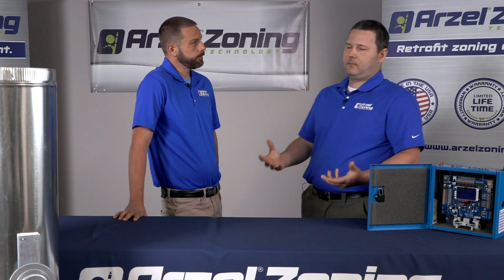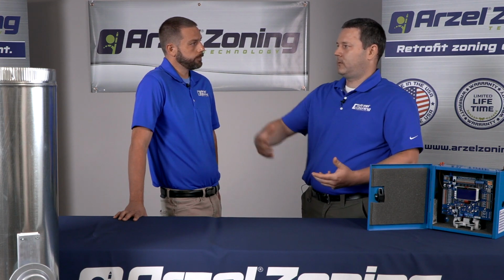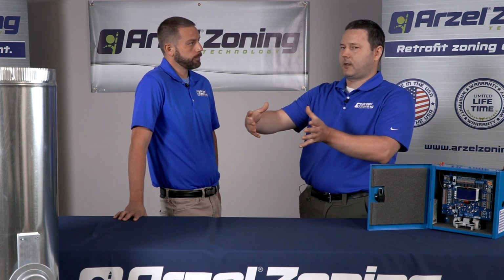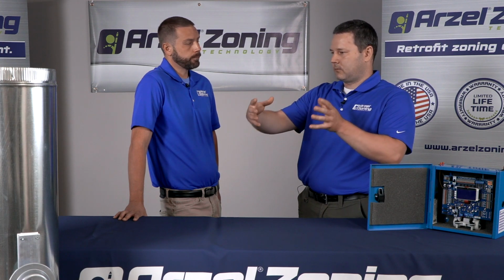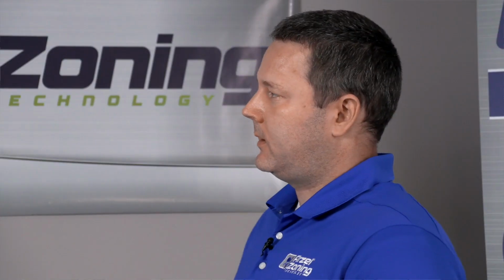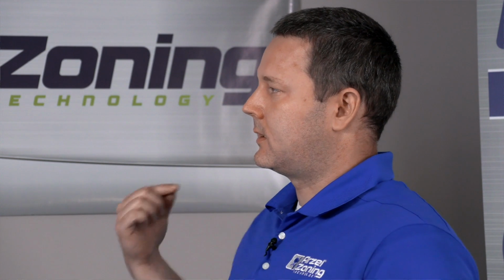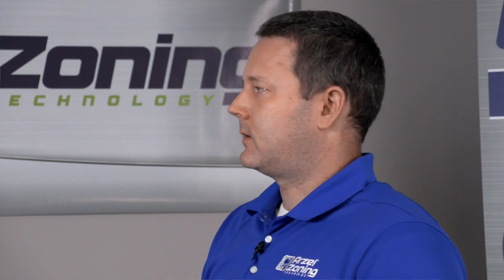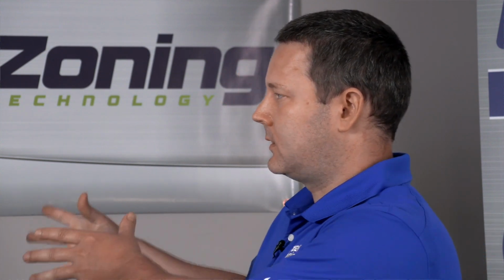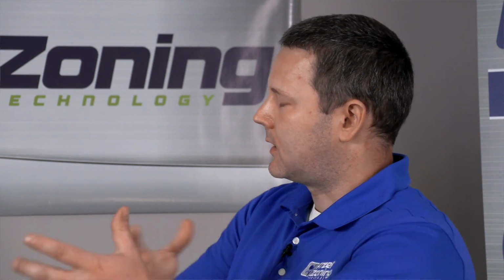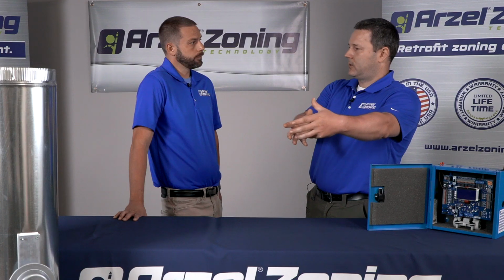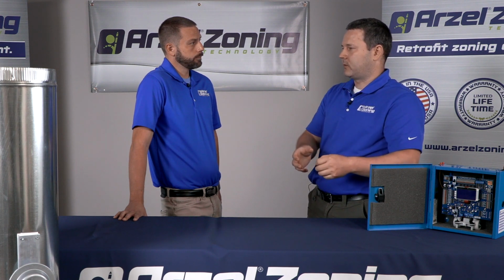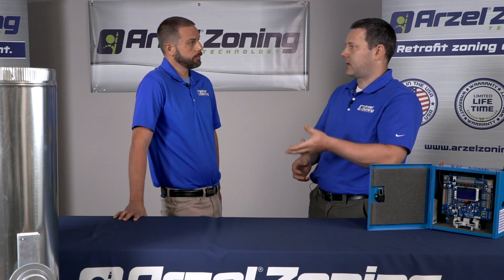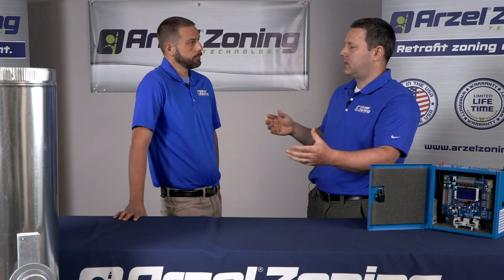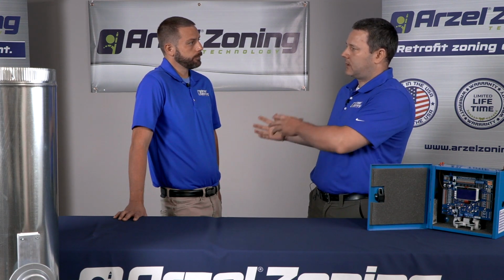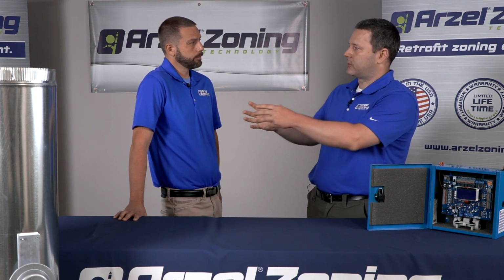So we have north, east, south, and west. A northern wind is cold, a southern wind is hot. That's going to change the thermal gain of the home. But you also have your sun rising and setting, and as it moves around the house, that creates thermal shift as well. It bakes this part of the house at this time of day, and that part of the house at that time of day. So when we're designing for zoning and split the home up, we might do upstairs and downstairs, or east and west, and that allows us to direct the air where that thermal shift is happening.